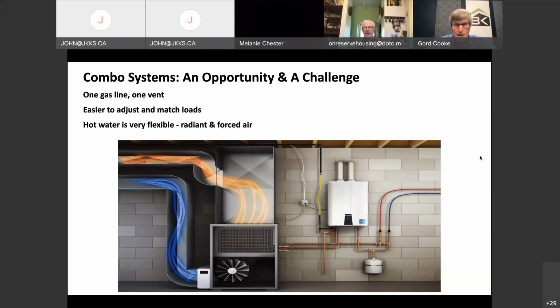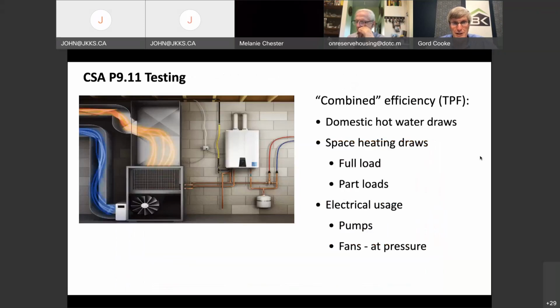I suspect the reason to mention these is because once you've invested in the efficiency of a really good water heater, say 95%, rather than buying yet another expensive gas appliance, you can just go to a much simpler air handler. You don't have to worry about venting it, and you just need your plumber to do the connection. So we're big fans of combo systems—that's where we like to get to.